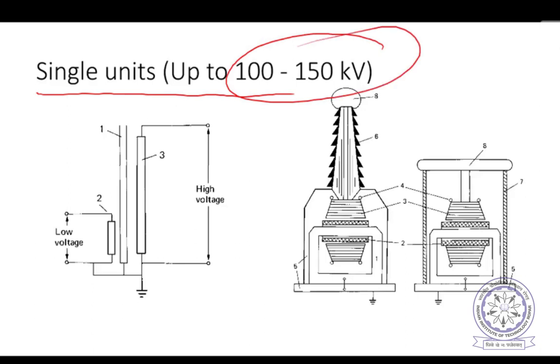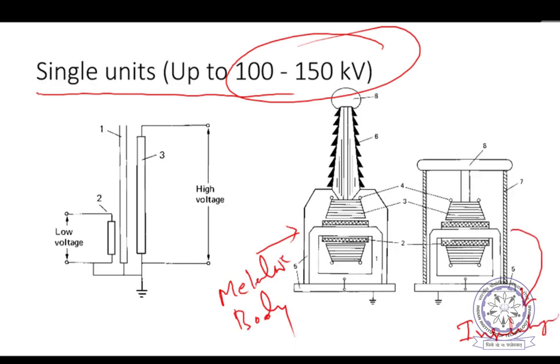There are two types of constructions given here. This is a metallic body, transformer, metallic body. And here, this is an insulating body. Due to the insulating and metallic body, there are minor constructional details. Apart from that, nothing is different. Both are the same. When a metallic body is used, when you are taking the high voltage terminal, you have to use a construction which is known as a bushing. You might have seen transformers outside with such a construction, with porcelain insulators. The high voltage lead is taken through this bushing inside using pipes, and then a spherical electrode which is at high voltage is kept here. This is the arrangement needed for the metallic body.